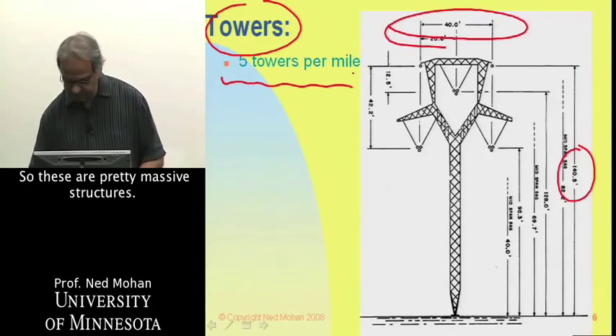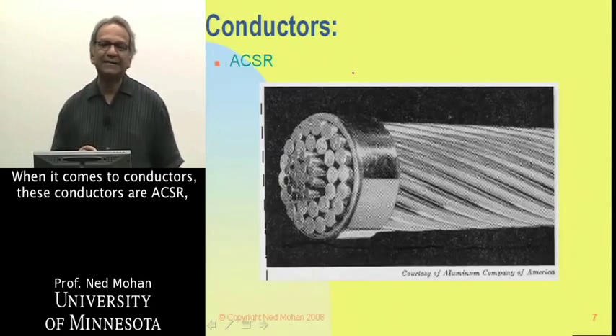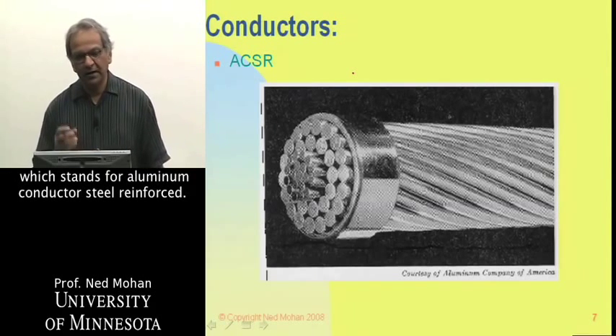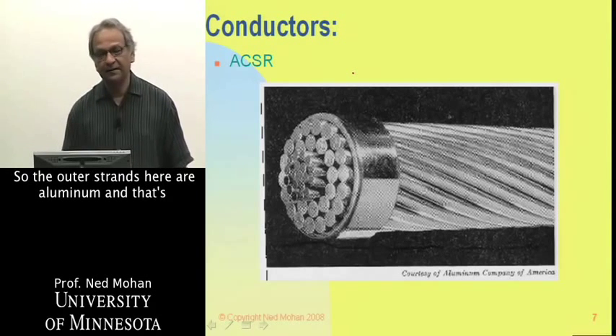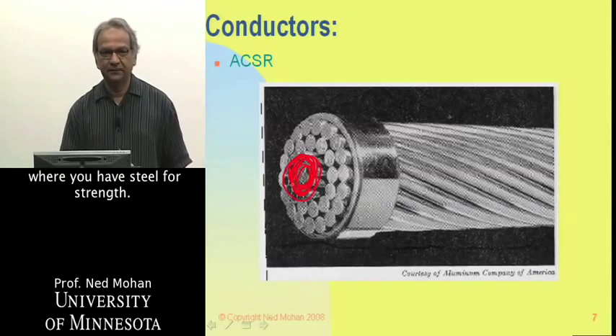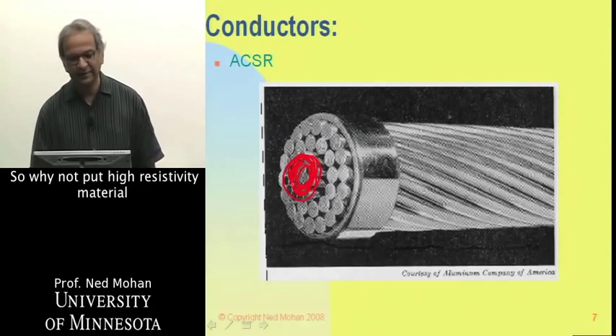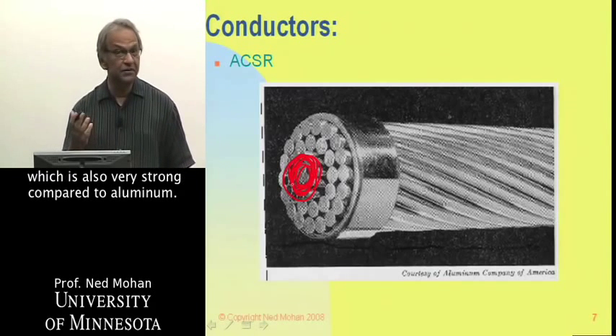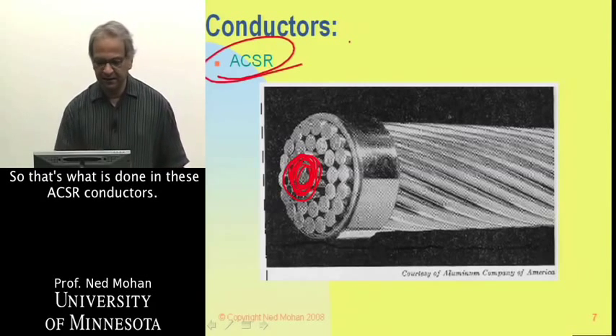These are pretty massive structures. When it comes to conductors, these are ACSR — Aluminum Conductor Steel Reinforced. The outer strands are aluminum, and that's where the current flows. But inside, there is steel for strength. Generally the current doesn't flow through the steel, so it makes sense to use a higher-resistivity but very strong material there. That's what is done in these ACSR conductors.